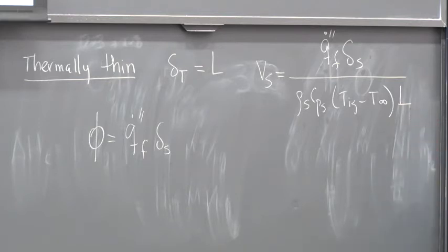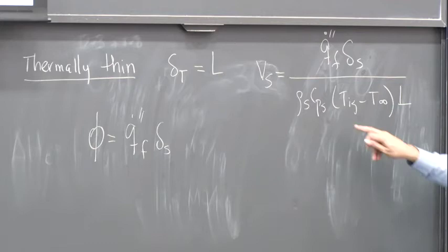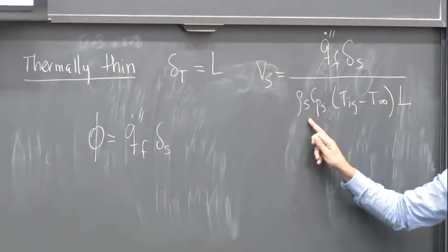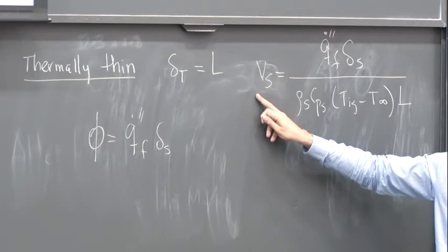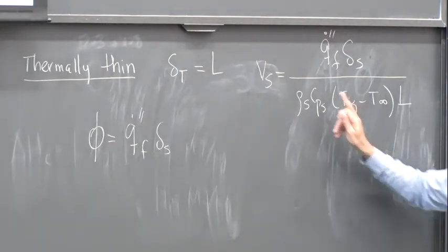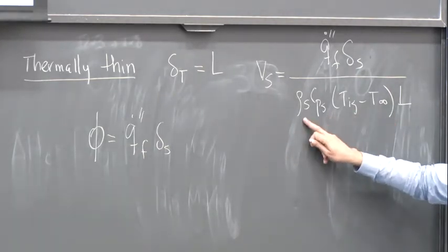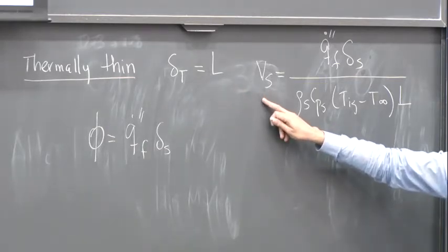Is that okay? So now I know that the density and the specific heat will dominate the flame spread. So if I have very low density, then what happens? Very fast flame spread. Is that okay? If I have a material with a very low ignition temperature, then I get very fast flame spread. I know which specific material properties will control the rate of flame spread.